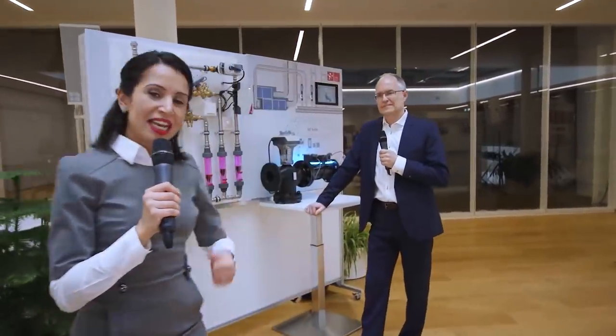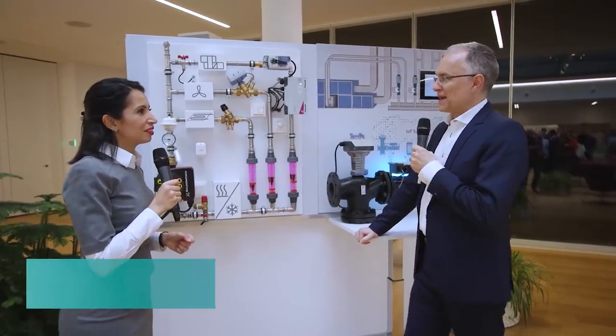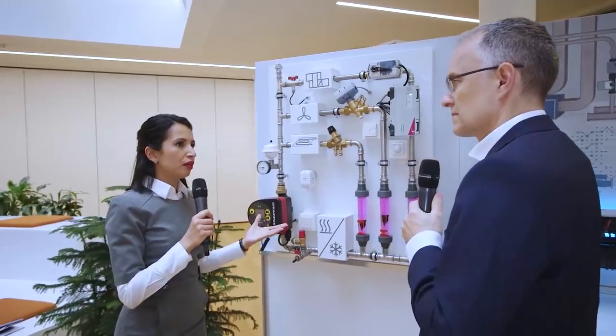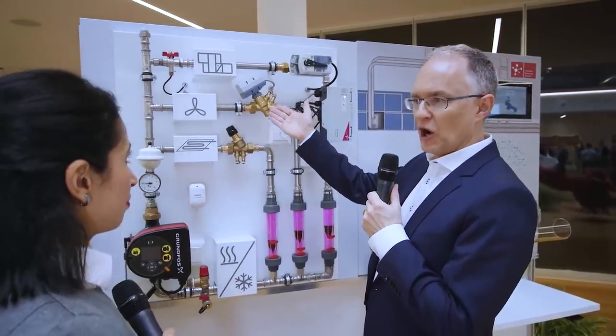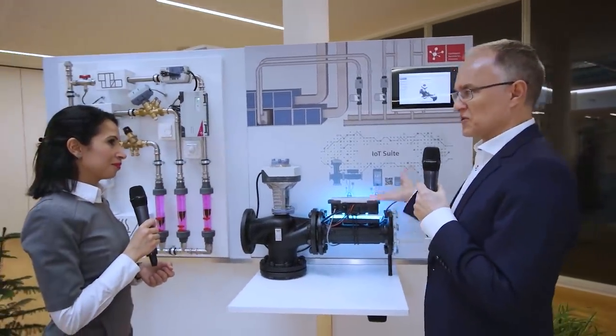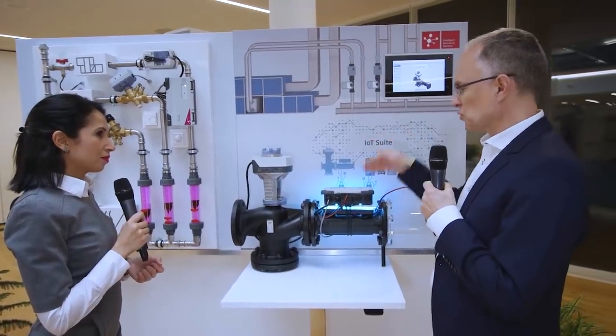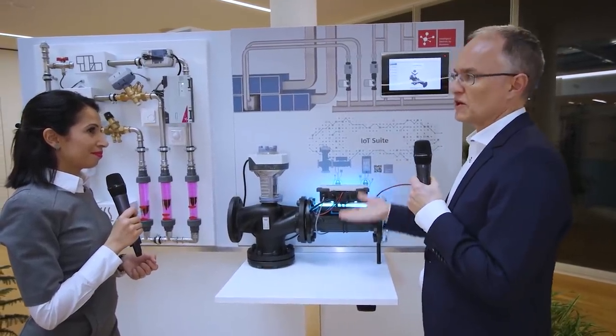Thank you so much, Pinar. Talking about smart devices, let's have an overview of the hydronic balancing panel. So Yannick, why is it important? Why is hydronic balancing important? Because you can save up to 25 percent of energy if you do this right. How do we really realize it? We use typically PICVs, or our latest introduction, the PICV on/off. How do we contribute with our PICVs to making buildings even smarter? We can go beyond that and have intelligent devices such as this intelligent valve, which not only provides much more data to the building to optimize, but can also react to the flow of energy — not just the flow of water — and this gives you another seven percent of energy savings on top.